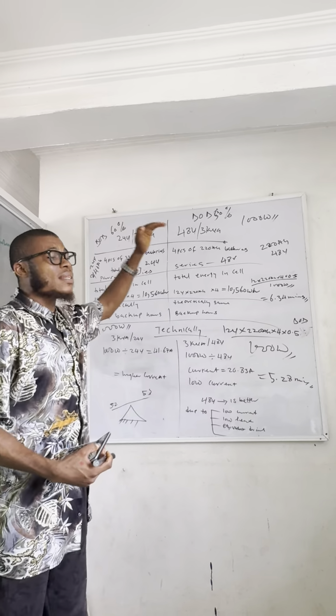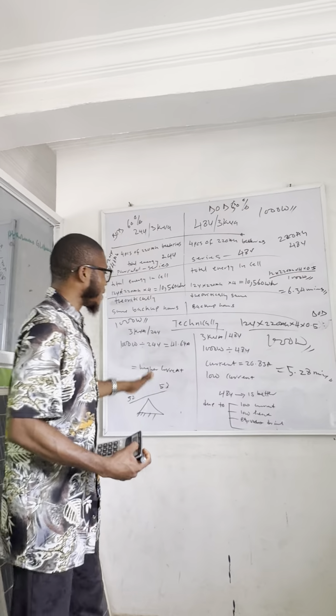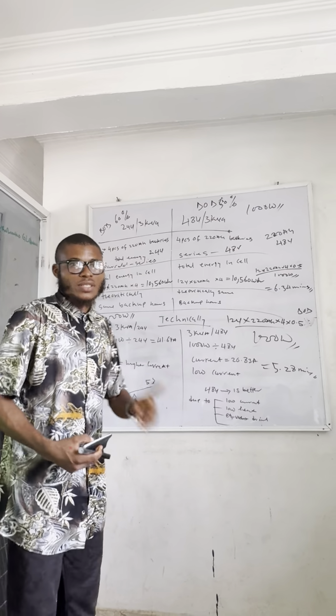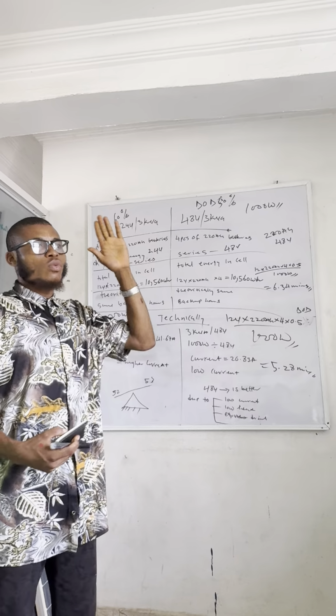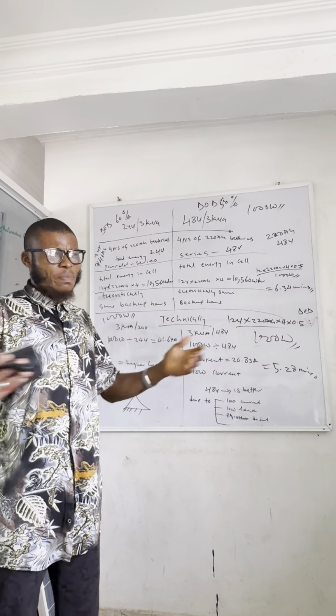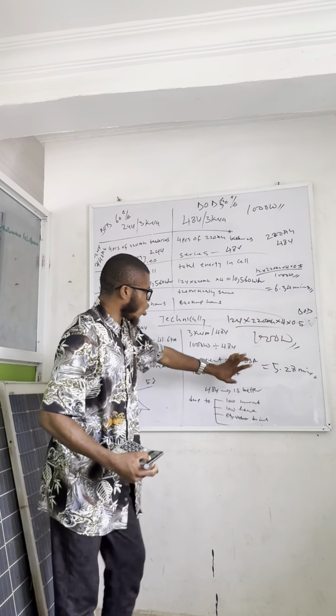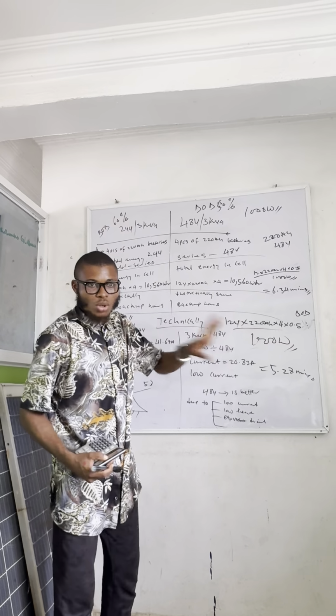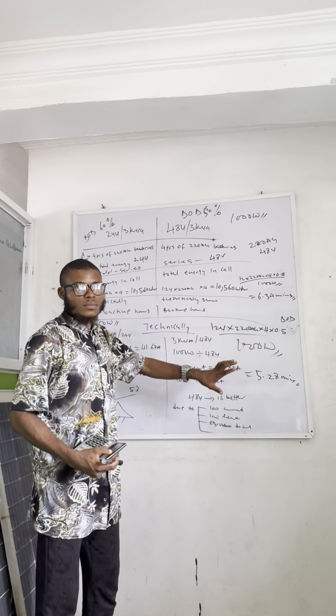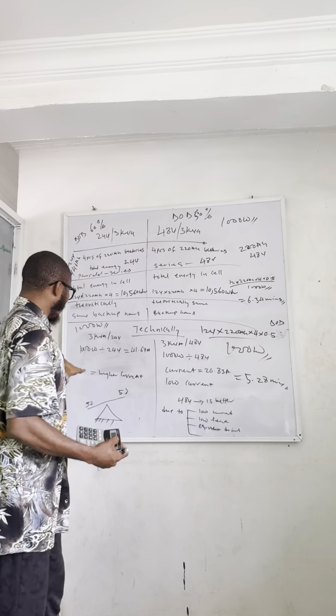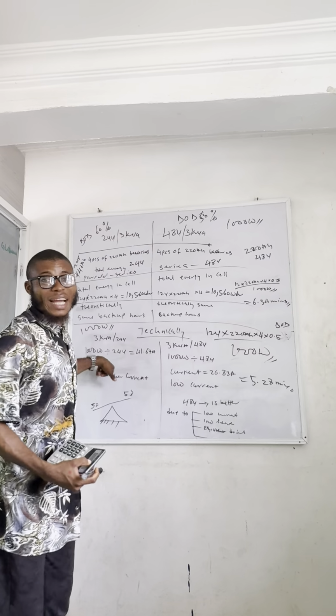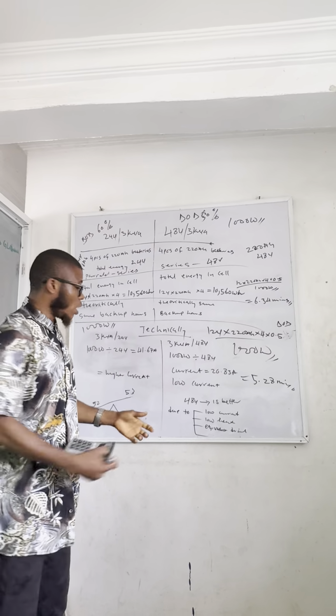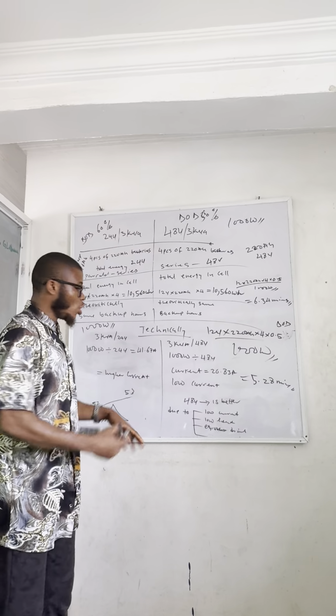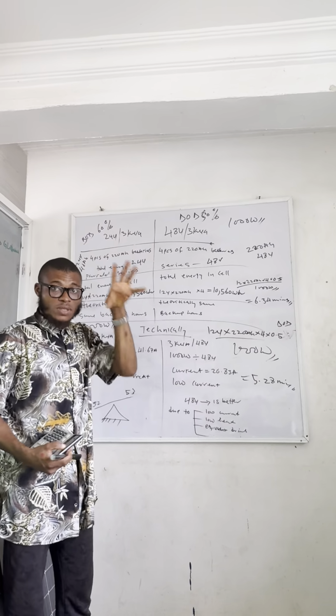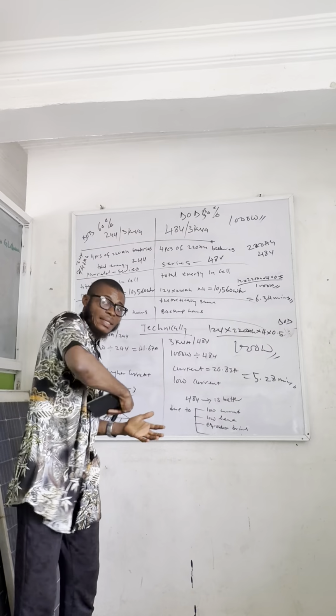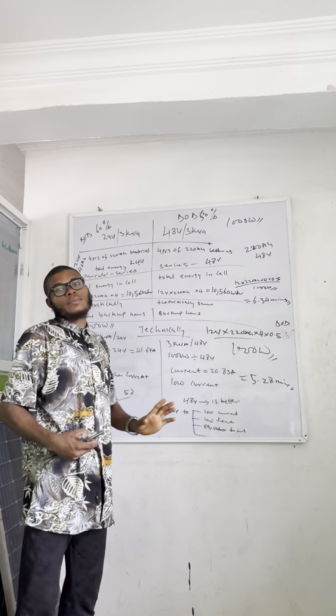When there is a higher discharge of current and there is a lower discharge of current, three things are going to happen. When you look at the heat, the temperature, everything, your 48 volt is going to last longer technically than your 24 volt, because the current of this one is higher. You will need a very strong cable. There won't be heat loss, there won't be any temperature rise. So your 48 volt, in terms of discharge and in terms of charging, is better. Thank you.